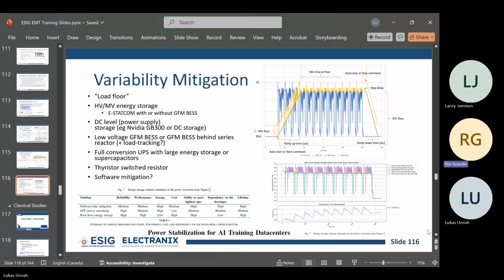There's nothing like that for voltage right now. But that's one of the arguments for picking a minimum and asking to maximize your ride through, because each manufacturer has a different ride through. And that was a main problem with the original PRC-024 at NERC. At the beginning of that project it was supposed to be a performance standard, which means if this profile happens at your interconnection point, you ride through.